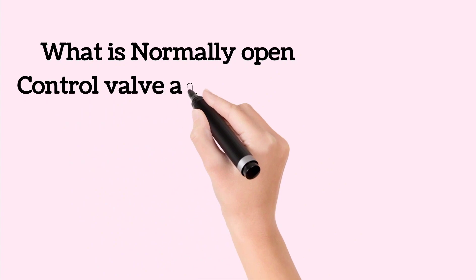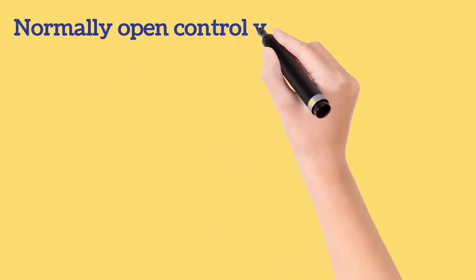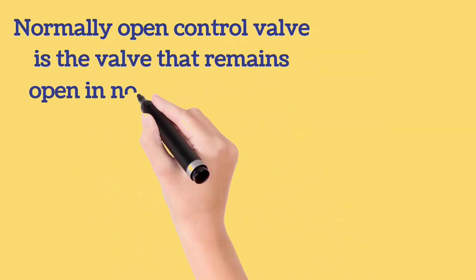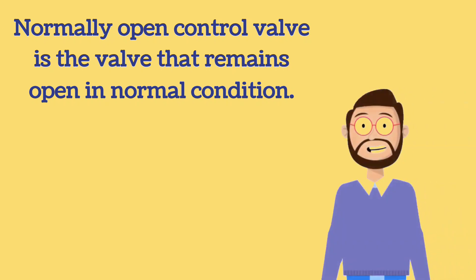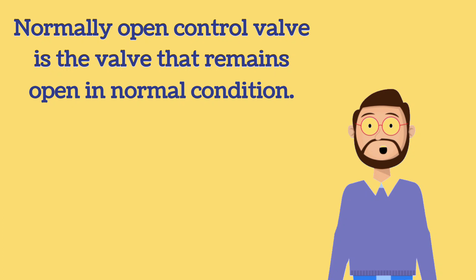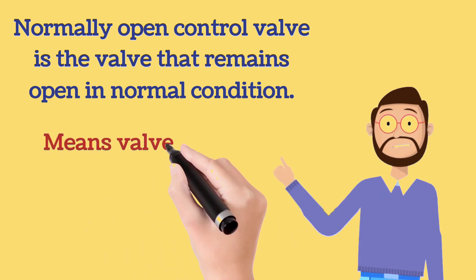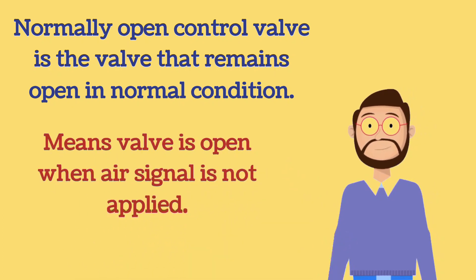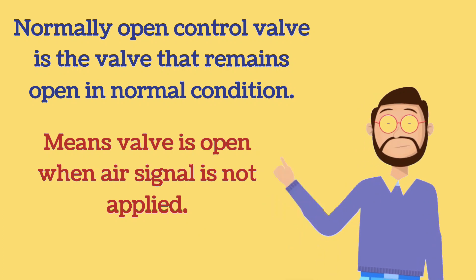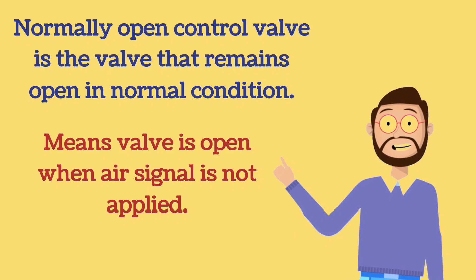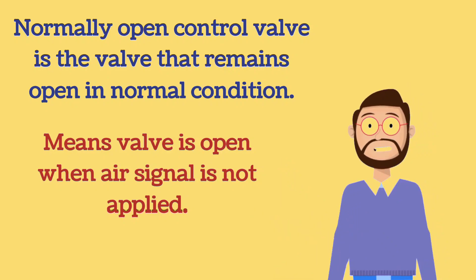The next question is: what is a normally open control valve and a normally closed control valve? A normally open control valve is one that is open in normal condition. Normal condition for a control valve means the absence of air — when the air signal is not applied. The valve that remains open in the absence of air is called a normally open control valve.